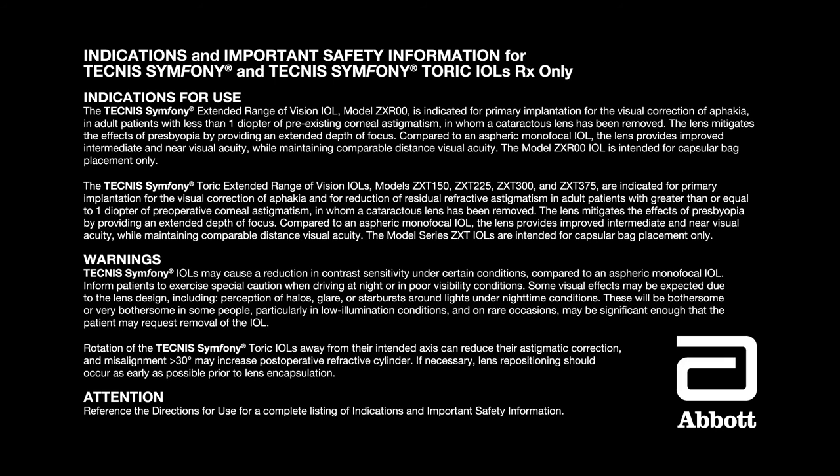Warnings: Tecnis Symfony IOLs may cause a reduction in contrast sensitivity under certain conditions compared to an aspheric monofocal IOL. Inform patients to exercise special caution when driving at night or in poor visibility conditions. Some visual effects may be expected due to the lens design, including perception of halos, glare, or starbursts around lights under nighttime conditions. These will be bothersome or very bothersome in some people, particularly in low illumination conditions, and on rare occasions may be significant enough that the patient may request removal of the IOL. Rotation of the Tecnis Symfony Toric IOLs away from their intended axis can reduce their astigmatic correction, and misalignment greater than 30 degrees may increase postoperative refractive cylinder. If necessary, lens repositioning should occur as early as possible prior to lens encapsulation. Reference the directions for use for a complete listing of indications and important safety information.